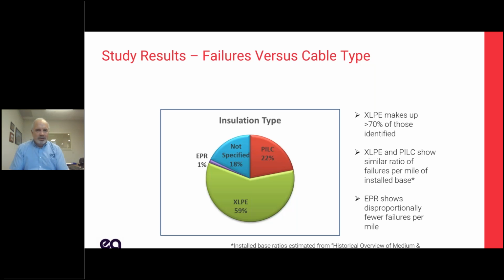So first thing we looked at was what type of insulation these reports are on. And we got XLPE, we got PILC, and we got EPR. And what we found was the XLPE and the PILC cables, the failure rates were pretty much in line with the ratios of installed cable that we got from a report from NETRAC. And so it's safe to say that the failure rates of XLPE and PILC are similar in our study. EPR was very low. It was 1% of all the cables that we tested. I don't have any information to tell me what that means. I wish I could tell you it means that EPR is much more reliable than XLPE. I don't know what that means, and we're trying to figure that out, but we don't have a good answer on that. Sometimes studies are like that.